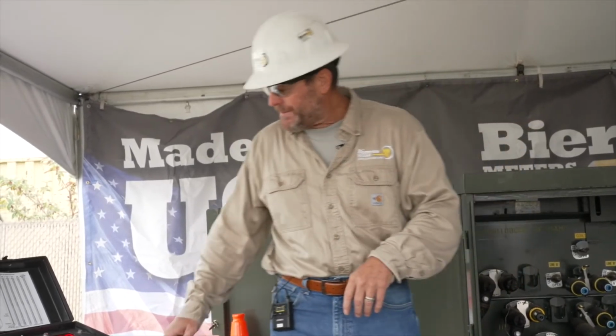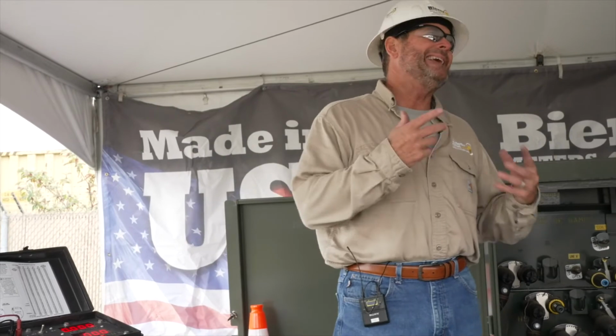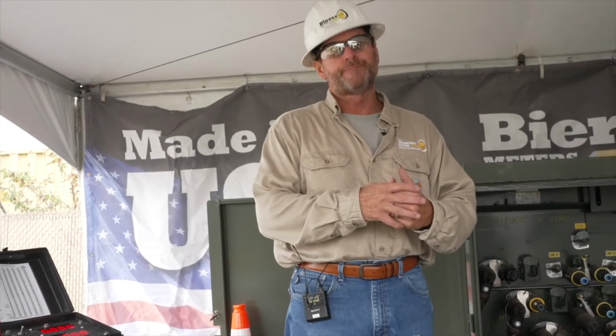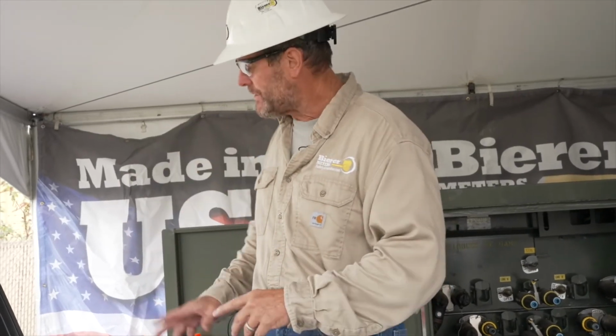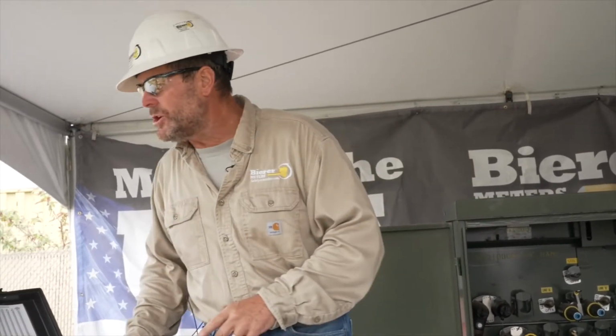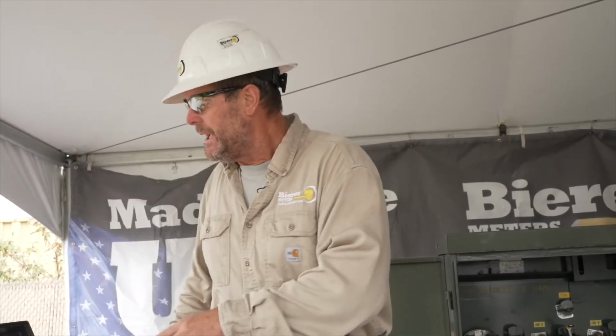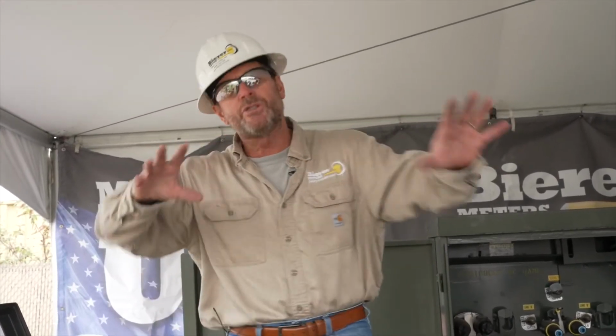You're also going to make sure that your ferrule is tight inside that clamp as well, no jiggling, no wiggling. So verify: if it looks good and tests good mechanically, it's typically going to take care of you, your best friend on the job site. If it gets hit by a potential fault current, it'll protect you.